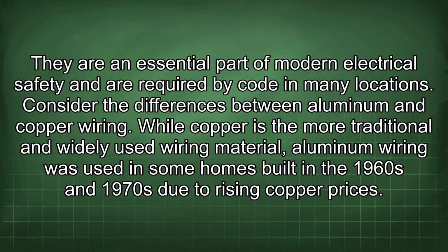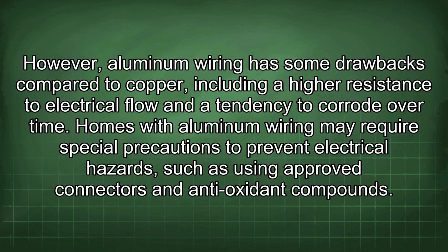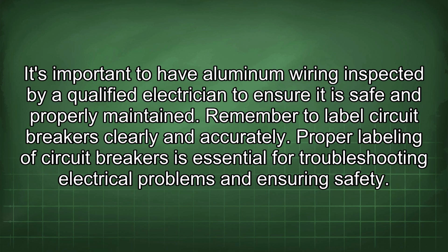Consider the differences between aluminum and copper wiring. While copper is the more traditional and widely used wiring material, aluminum wiring was used in some homes built in the 1960s and 1970s due to rising copper prices. However, aluminum wiring has some drawbacks compared to copper, including a higher resistance to electrical flow and a tendency to corrode over time. Homes with aluminum wiring may require special precautions to prevent electrical hazards, such as using approved connectors and antioxidant compounds.